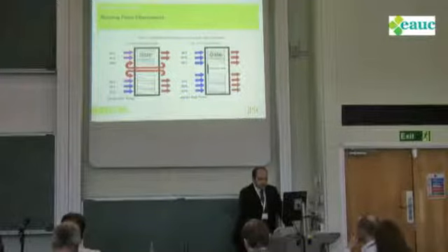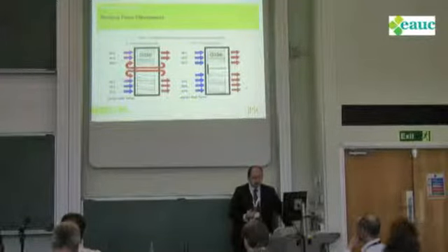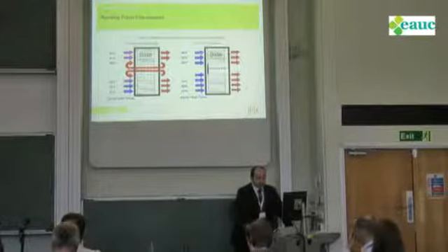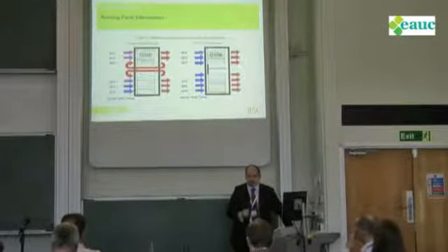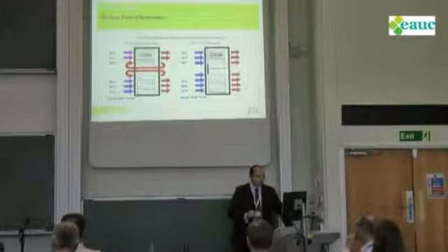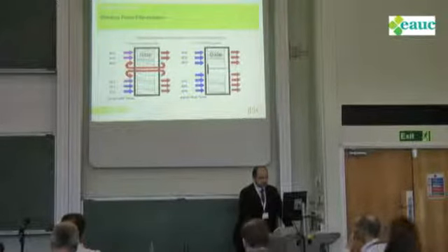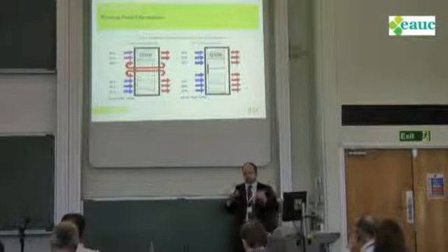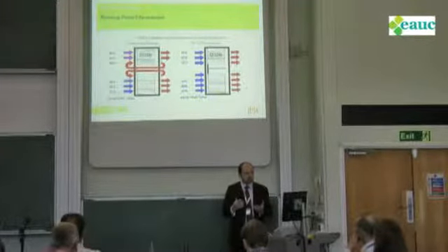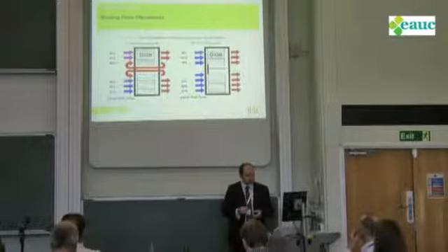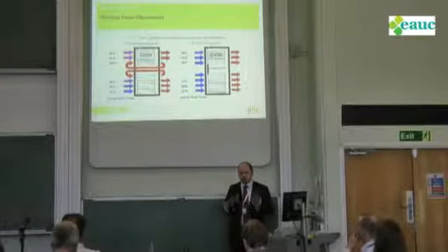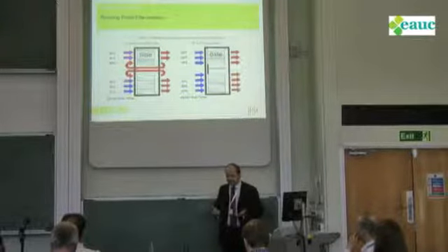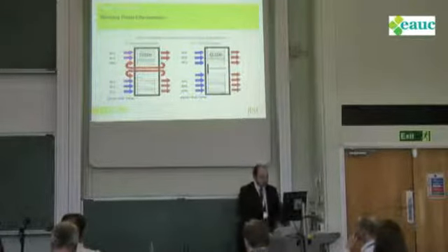So just by putting blanking panels in, you're preventing the hot air from coming back. You can see that now the cold air maintains a level of consistency up the front of the rack. You can improve these temperatures by containing the cold air, so you get much better consistency as well. But whether you contain a cold aisle or hot aisle doesn't really matter. That you're containing the aisles is the key point.